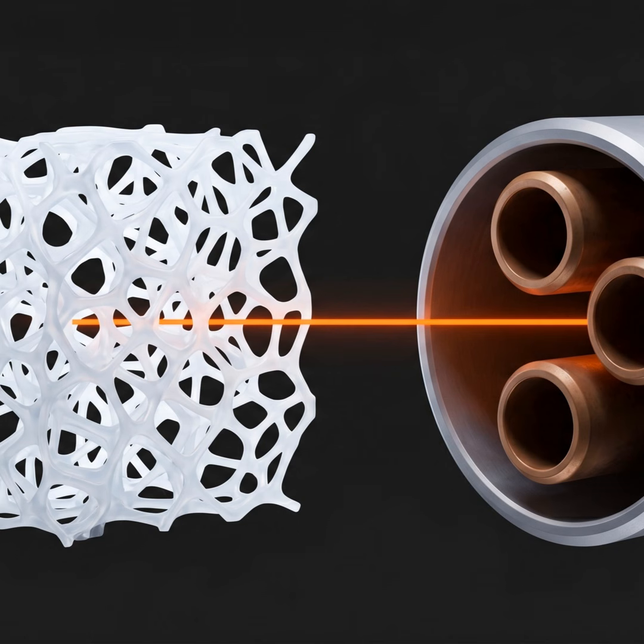Wow. That is literally violent boiling heat. Yep. And it's just a byproduct of making things cold somewhere else in the building. It is a massive thermal burden. Now, the factory has to do something with this 250-degree gas because the refrigeration cycle cannot continue until that gas is cooled down and condensed back into a liquid state. Right, you have to shed the heat.